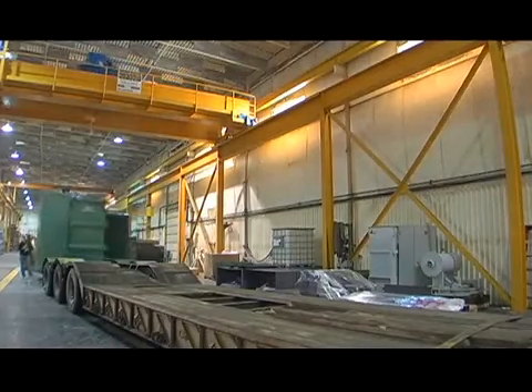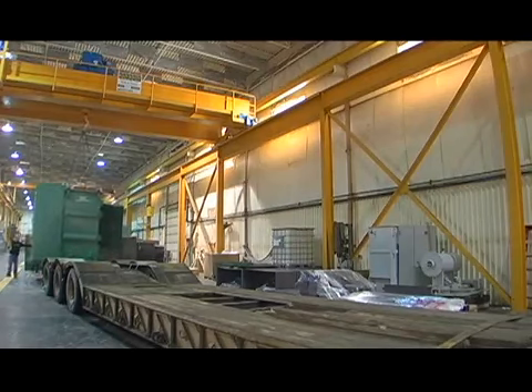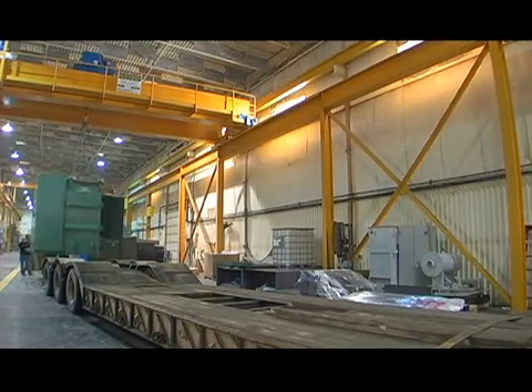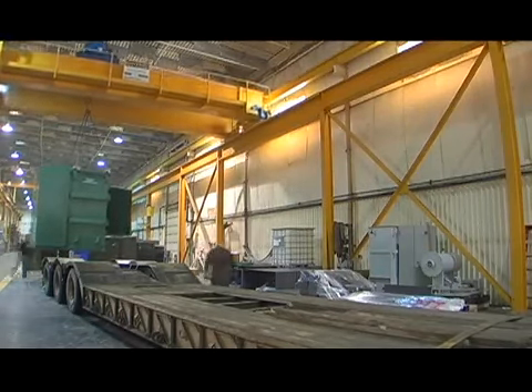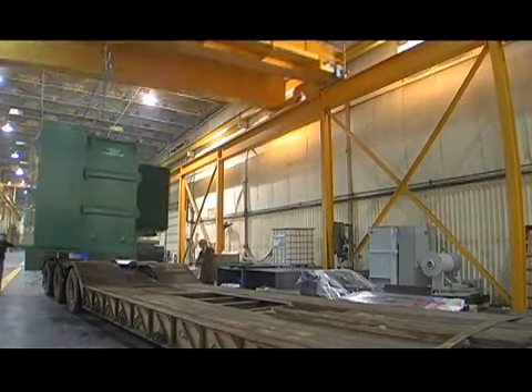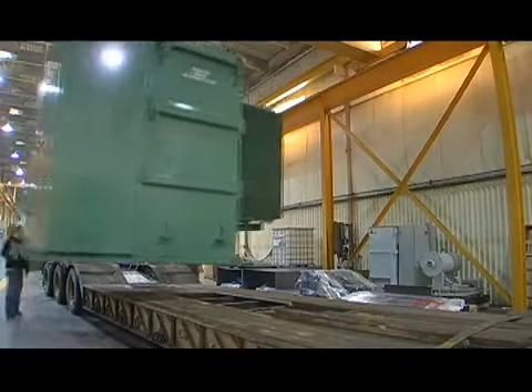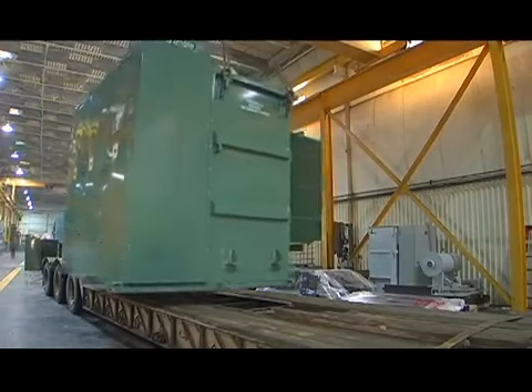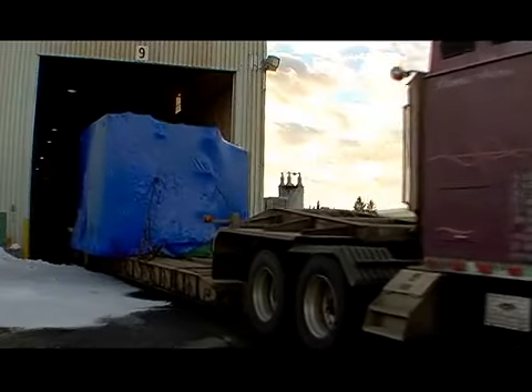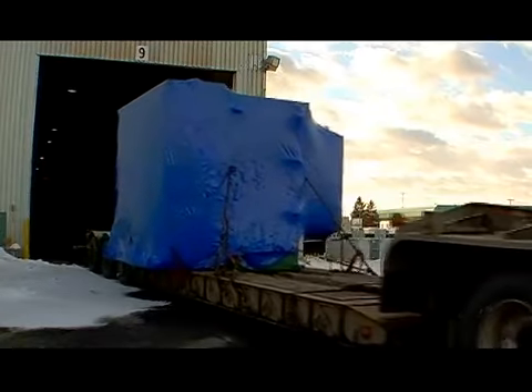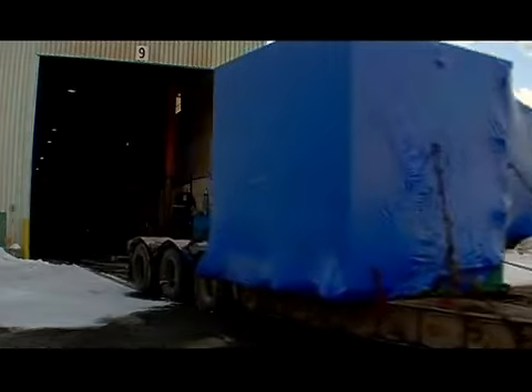The high-voltage pad mount transformer leaves the factory completely assembled and ready to be installed. Another feature of the HV pad mount is that it is shipped completely assembled. The rads are on, it's completely oil filled, so there's absolutely no oil filling required on site, which is a big advantage of the HV pad mount. It leaves our factory assembled, sits on a truck, and you can literally take this unit, put it on the pad, run the cables to the HV and LV bushing, and it's ready to go. There's no on-site assembly at all.